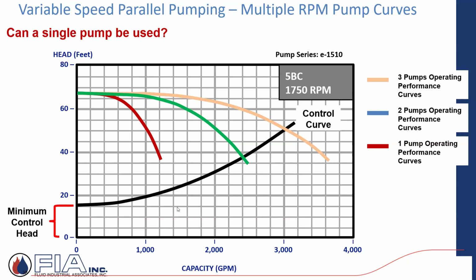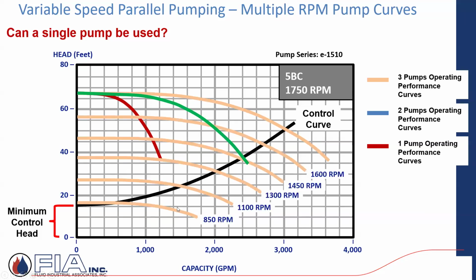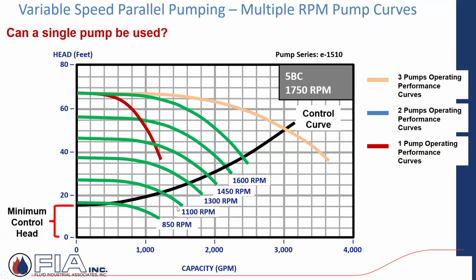And I have this minimum control head that's going on out in the system. In this case, it's just under 20 feet. So the system curve starts not at 0, but just at the base of that minimum control head of maybe 18 feet of head. So the question is, can a single pump be used? So variable speed with all three pumps running, and that's kind of reflecting how it would operate somewhere on that curve. If I shut off one of the pumps and I only ran two of them and they were in parallel, and I'm changing the speed of both pumps, here's my operational points.